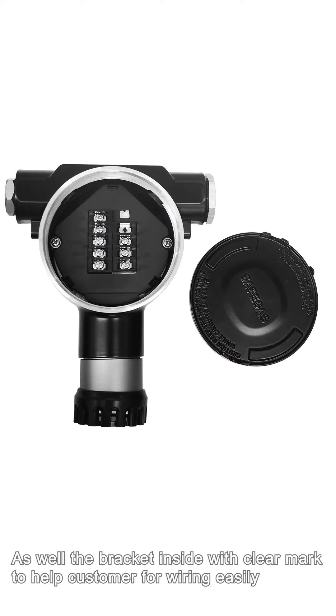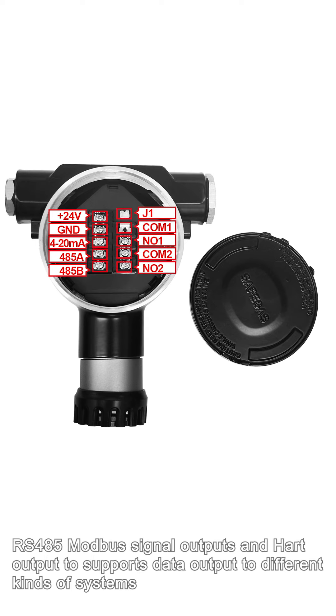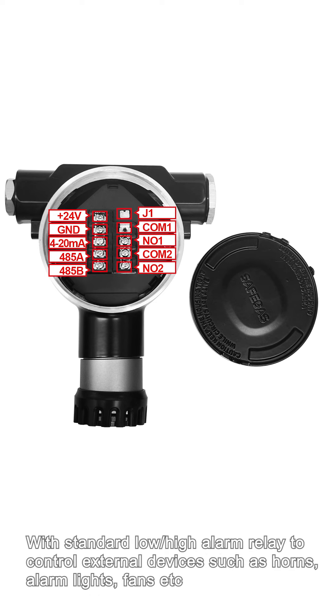The bracket inside has clear markings to help customers with wiring easily. It integrates a three-wire 4 to 20 mA analog signal output, RS-485 Modbus signal output, and Hart output to support data output to different kinds of systems. With standard low and high alarm relays to control external devices such as horns, alarm lights, and fans.